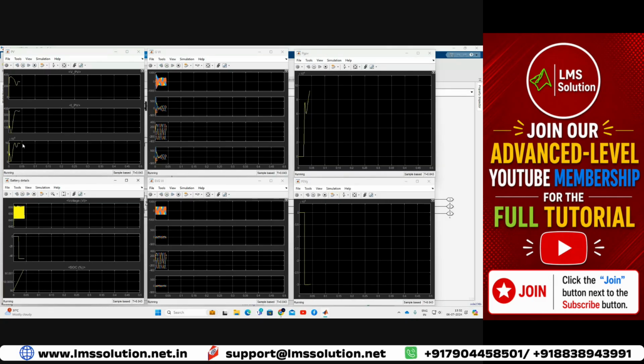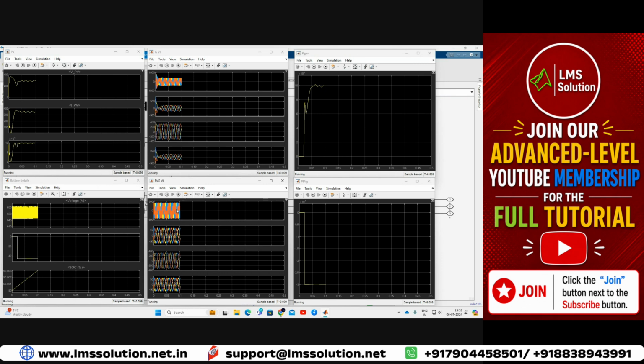Voltage. Here you will see the power generation from the PV is around 100 kilowatt, and then this is the inverter voltage, inverter current, grid voltage, grid current on the PV inverter side, and then the power from that PV grid inverter. Here you will see the battery voltage, battery current, battery in charging mode, and here you will see the EV charger inverter voltage, current, grid side voltage and current. This is the power in the inverter. This is around 30 kilowatt.